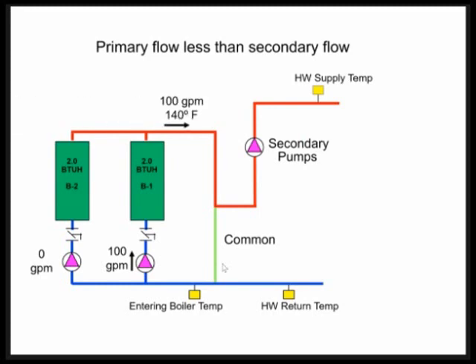So we're running at 2 million BTUs. Let's say we're in a hotel, and there's a conference room or a ballroom down the hall, and they decided to open it up for an event. Maybe that room was kept at a lower temperature. When that room is finally turned on or set into occupied mode, the two-way valves go open on the air handling units, and we get a dump of water into the loop, right? Or we get a load dumped into the loop. When that happens, the flow rate's going to go up in the secondary. So all of a sudden, our flow rate goes up to 150 GPM when it was at 100 GPM. Now I have 50 GPM in my common pipe, but it's going up this way and mixing here.